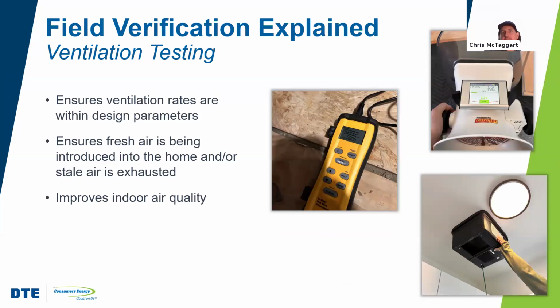Ventilation testing is a very critical element, and how we test depends on what system is installed — there's a variety of tools. We're showing a hot wire anemometer, typically used for testing balanced or supply-based ventilation systems. Top right is a powered flow hood, an extremely accurate tool often used for testing either supply or exhaust-based measurements, very accurate in either direction. Bottom right is an exhaust flow box device, a relatively simple tool mainly used for testing exhausts, though it may also be appropriate for some low flow supply measurements.